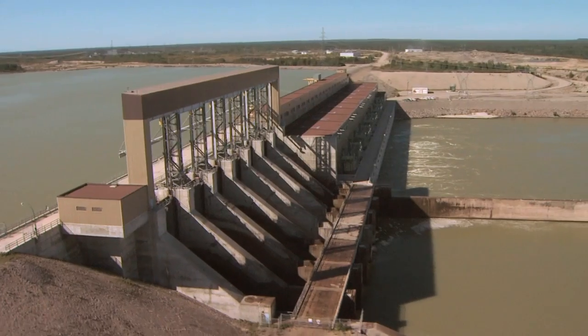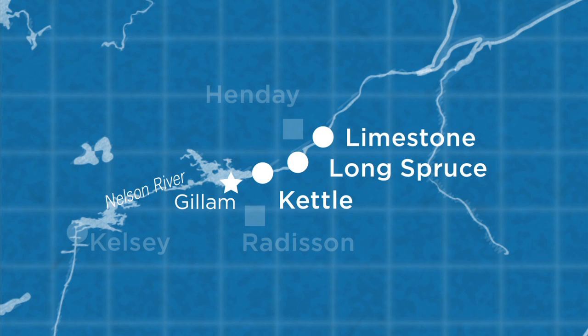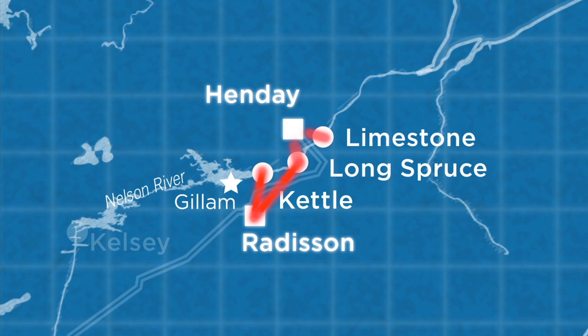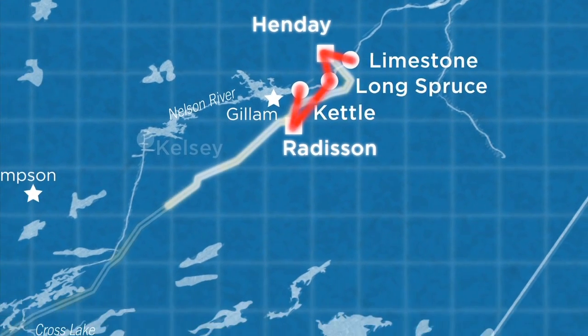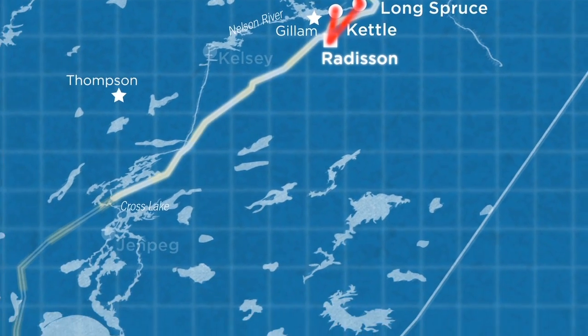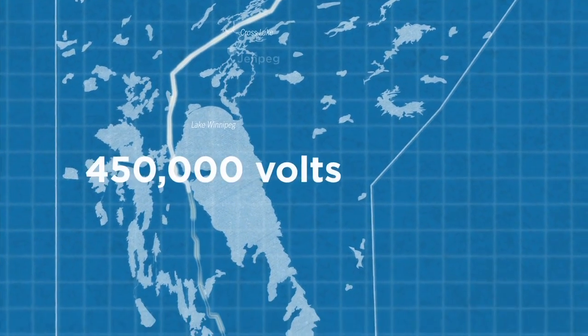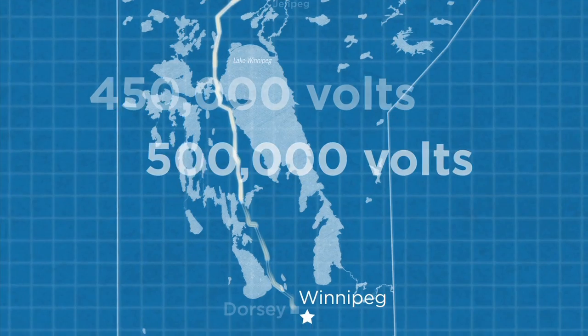The system works like this. Electricity is generated in alternating current at Kettle, Long Spruce, and Limestone generating stations. Transmission lines carry that power to Radisson and Henday converter stations, where it is converted into direct current. The DC power flows south on two 900-kilometer HVDC transmission lines, Bipoles 1 and 2, that operate at 450,000 and 500,000 volts respectively.